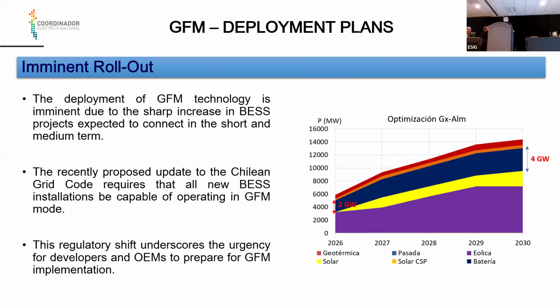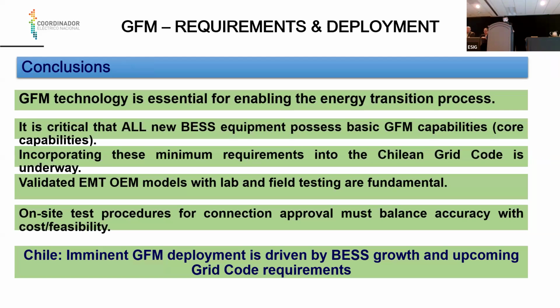So we are now in an imminent rollout of grid forming because the BESS are expected to be connected. There is a boom of BESS in Chile. Well, the principal highlights for us are: grid forming technology is essential to enable our energy transition process. We value that the EMT models with lab testing are necessary, and the on-site procedures for connection approval must balance accuracy and cost feasibility. Thank you.